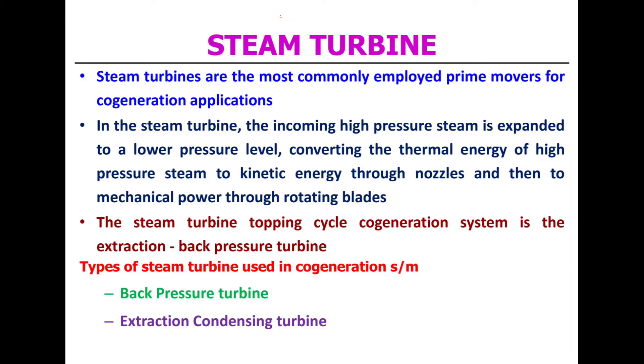According to the steam turbine, steam turbines are the most commonly employed prime movers for cogeneration applications. In the steam turbine, the incoming high pressure steam is expanded to a lower pressure level, converting the thermal energy of high pressure steam to kinetic energy through a nozzle, and then to mechanical power through rotating blades. The steam turbine topping cycle cogeneration system is the extraction backpressure turbine.